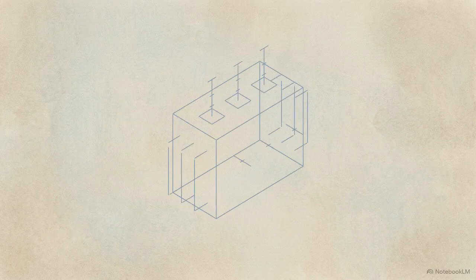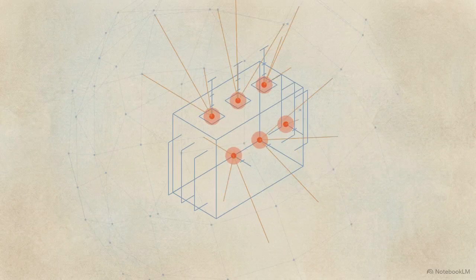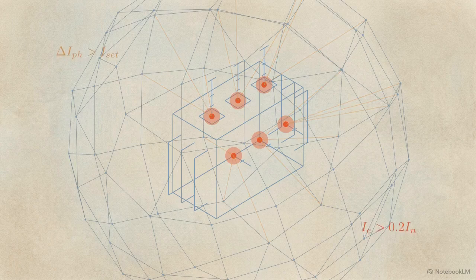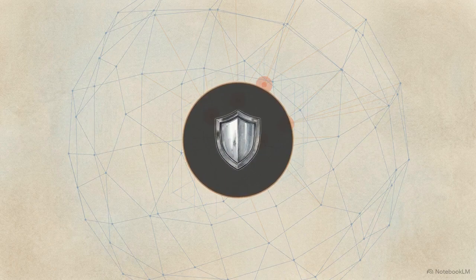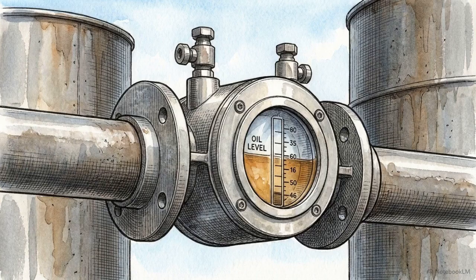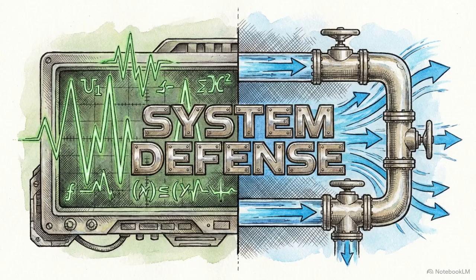The first layer is a calibrated electrical matrix, a network of sensors calculating exact phase and earth fault thresholds. The second layer steps outside the electrical domain entirely. It uses a hydromechanical failsafe, the Buchholz relay, to detect the physical byproducts of internal degradation. Unprotected faults are violent thermal events requiring a multi-physics, highly calibrated shield to prevent the destruction of the unit and hazards associated with oil decomposition.